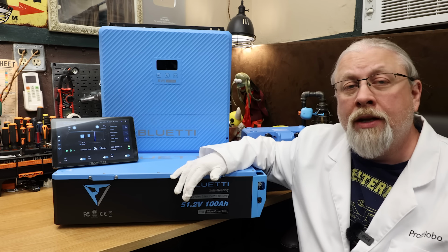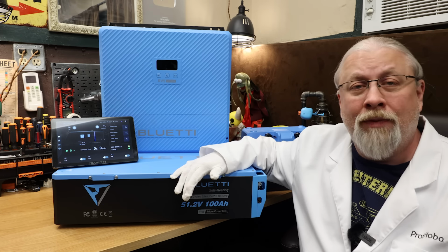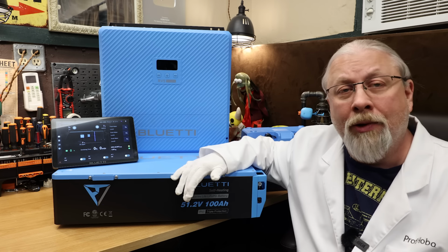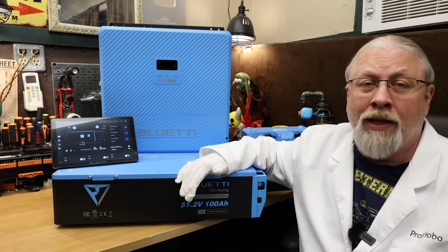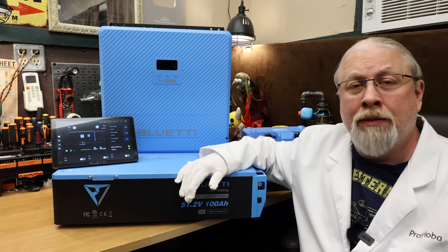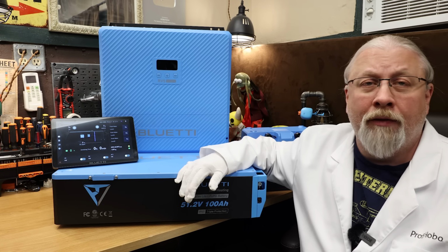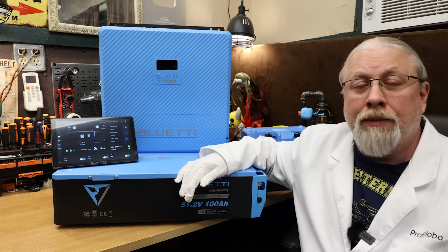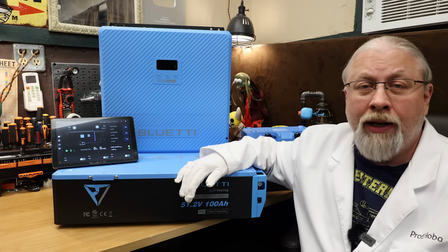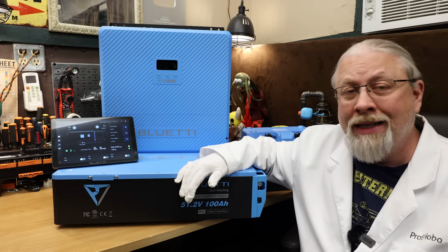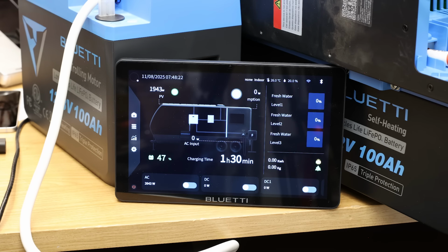As for the charging fan noise, at AC maximum 5,000 watt rate it was 54 decibels, about the same as the inverter level at maximum. At AC minimum, or quiet mode, it was a much quieter 44 decibels. Simultaneous charging ability is supported up to the solar maximum, or as I tested, 2,000 watts, solar priority.